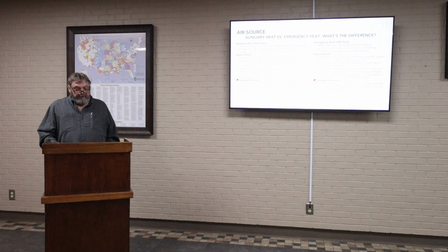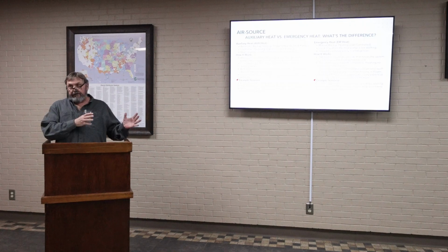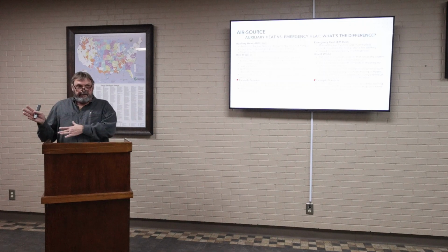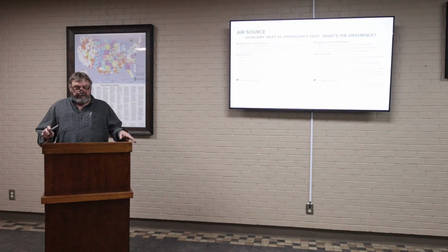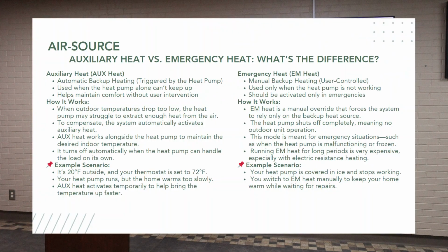So that's the auxiliary heat, and we don't want to confuse auxiliary heat with emergency heat. If you're talking auxiliary heat, that is some source of fuel that's going to work in conjunction with your heat pump. Your heat pump is going to crank along all it can, and when I set this thermostat on 72 and the heat pump says, hey, I can't get there, it's going to kick in your auxiliary heat, whether it's heating strips or gas or whatever your other source is, usually those two, right?